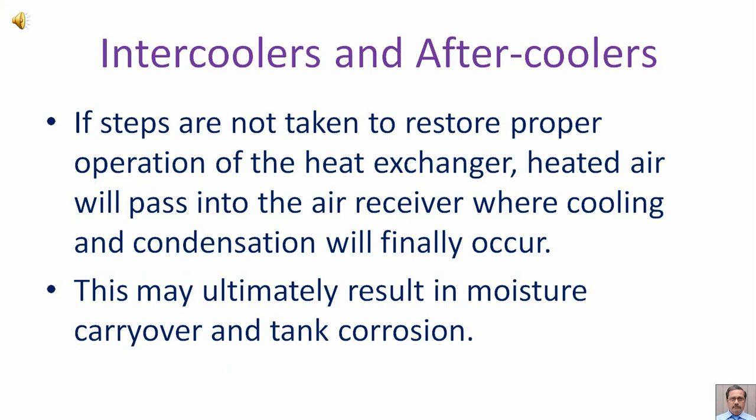If steps are not taken to restore proper operation of the heat exchanger, heated air will pass into the air receiver where cooling and condensation will finally occur. This may ultimately result in moisture carry-over, heat exchanger and tank corrosion.